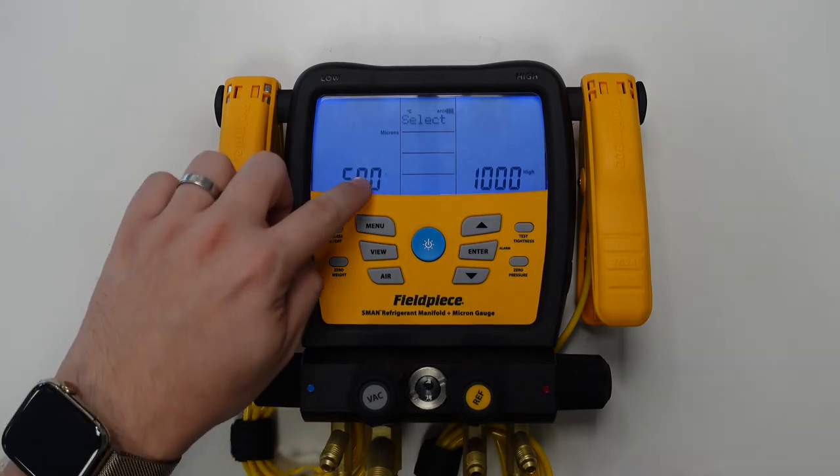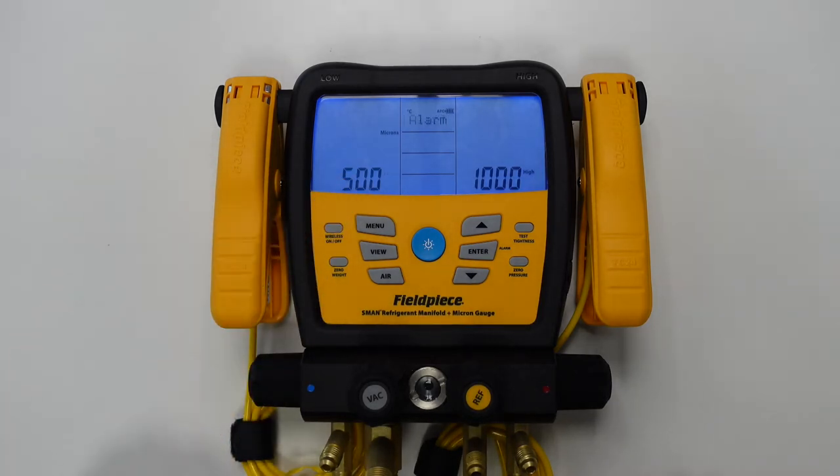And so you'll see here that the low vacuum alarm is flashing, which means we currently have that value selected. The default value setting for this on our manifolds is 500 microns, but we can change this to suit the system we're working on.